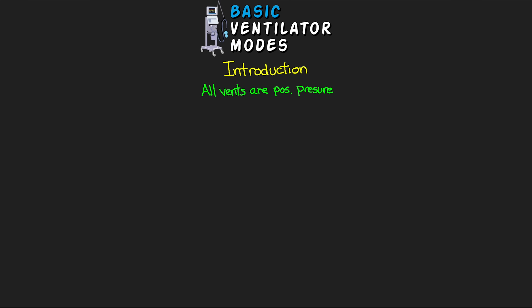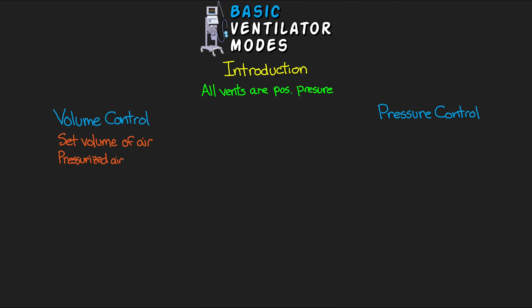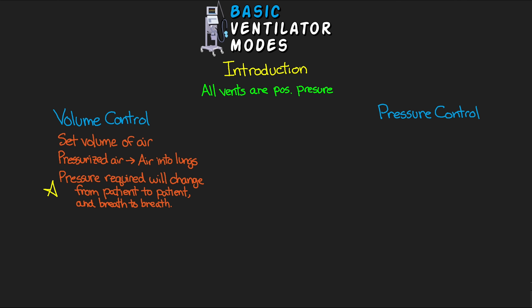There are really two main categories you're going to come across. The first is something we call volume control, and the other is pressure control. With volume control, the basis is that we're going to be setting and controlling the volume of air that our patients get. The vent delivers this volume by providing pressurized air, causing it to move into the patient's lungs. Depending on many factors, the pressure required to deliver this volume can and will change from patient to patient and breath to breath.